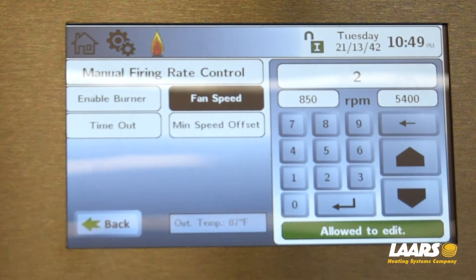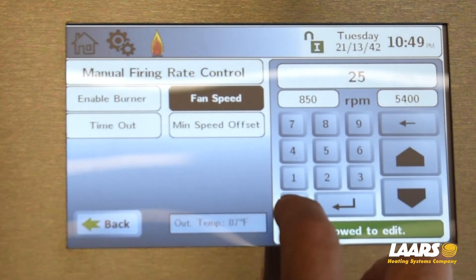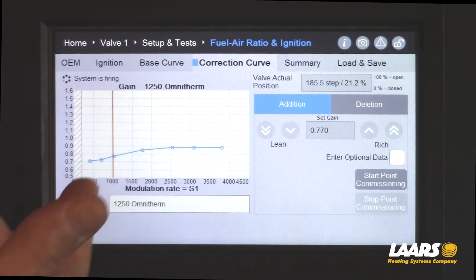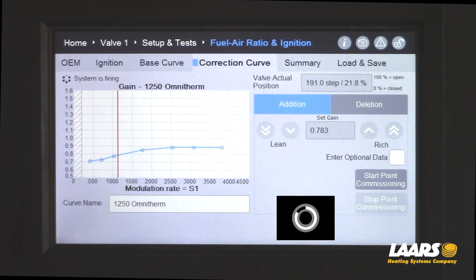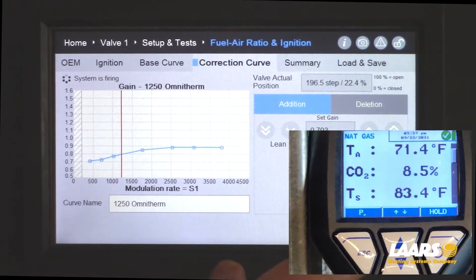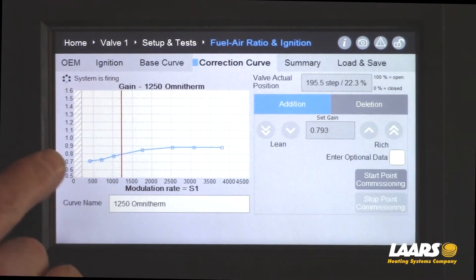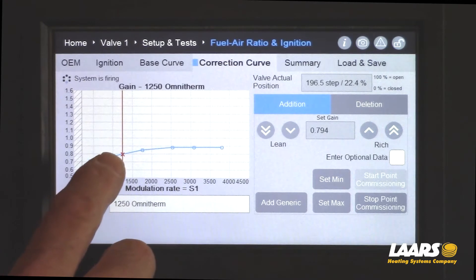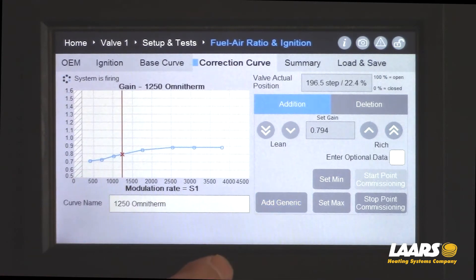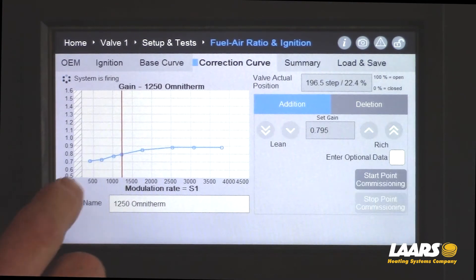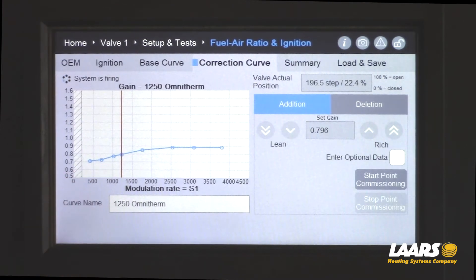The next point is going to be 1250 RPMs. Be patient and wait for the air indicator line to come up on the fuel line. Here we are at 1250 — we're dialed in. If you have to make a change, click start point commissioning and change it. To add another point, click start point commissioning again — this is another generic point. Click add generic. We will now have four points, and we're going to continue this process.